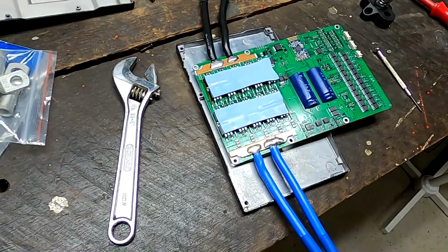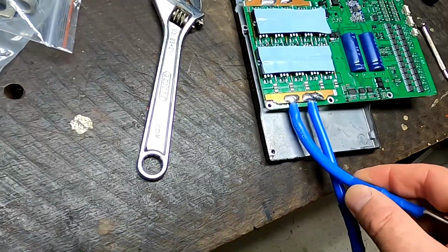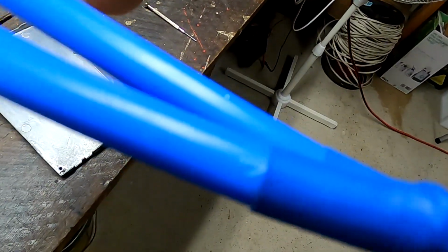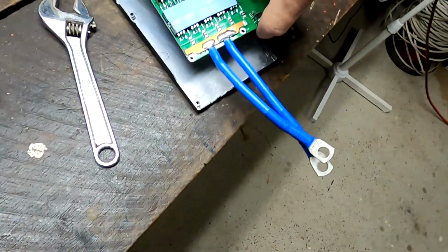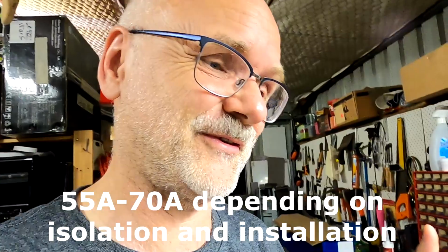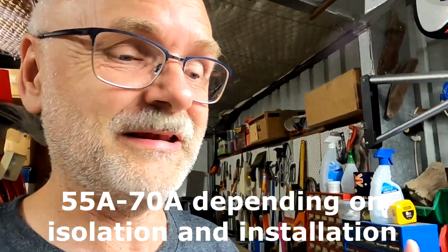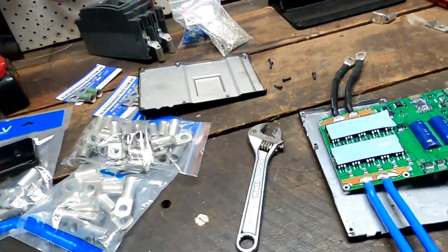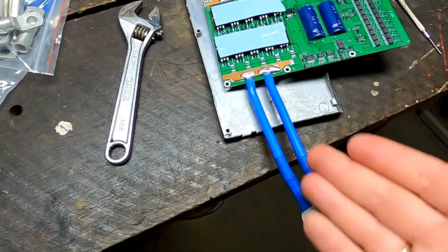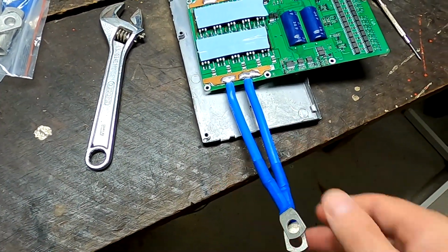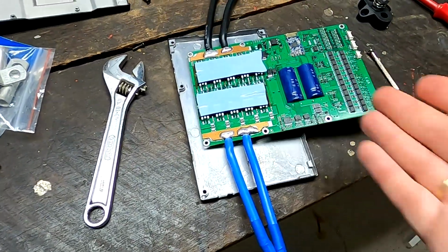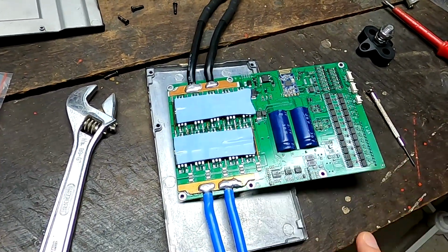Now, this is a 7 gauge wire, which is 10.55 square millimeter. This is good for about 55, 60 amps, 57 you can find online. So times 2, we've got roughly 100 amps carrying capacity of these two cables. The BMS is specified with 200 amps continuous current.